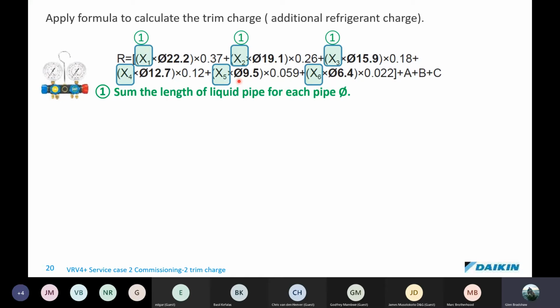First of all, we need to know the sum of the liquid line pipes for each pipe diameter. Okay, so we don't want a total length of just given to us, 150 meters of liquid line. We need to know the length per diameter. So much half-inch piping, so much 3/8 piping, so much 1/4-inch piping, for instance. That's what's required in the calculation. Each of these dimensions, okay, is then multiplied against a factor. Okay, so here you see diameter 22.2. This would be 7/8 inch liquid line, and that is multiplied with a factor in there.